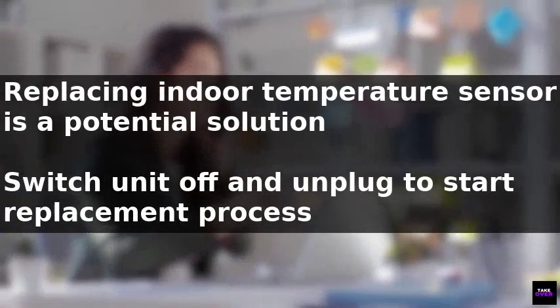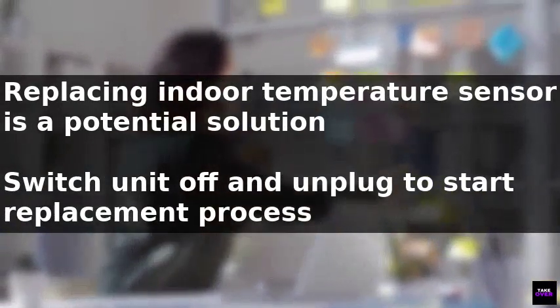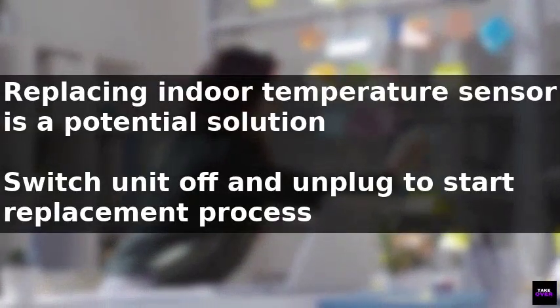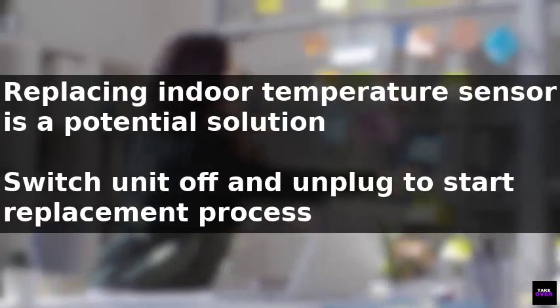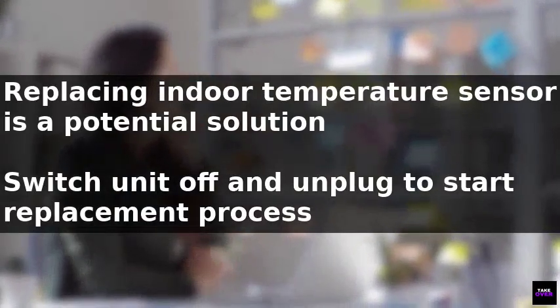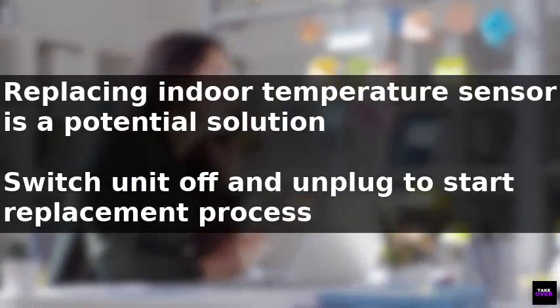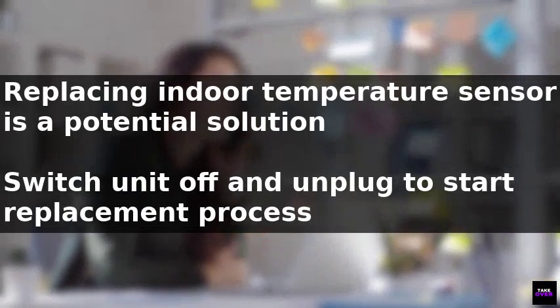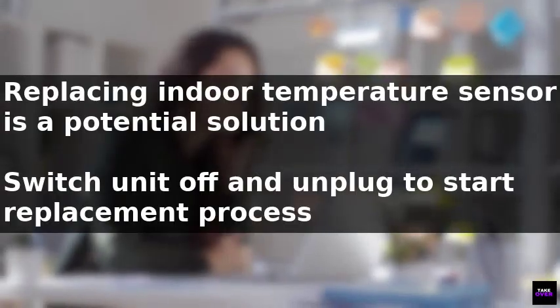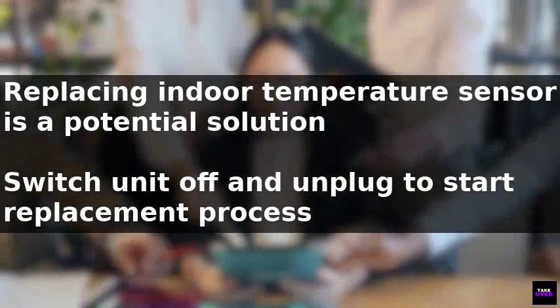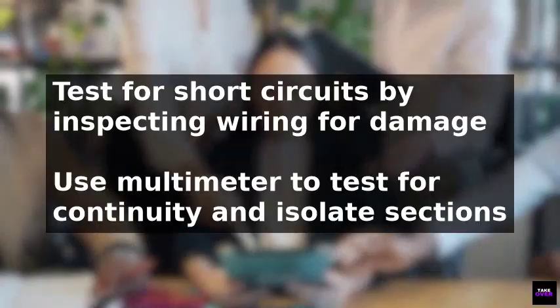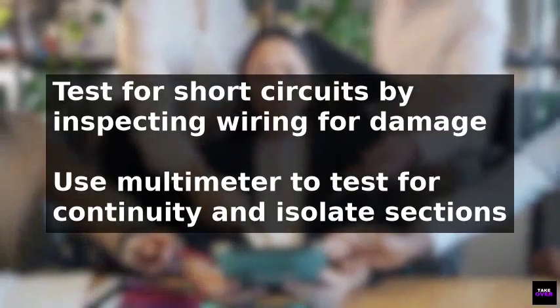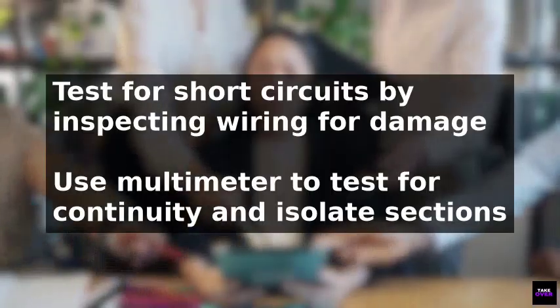This can be done by switching the unit off, unplugging it, removing the plastic cover, locating the temperature sensor, labeling the wiring, removing the faulty sensor, installing a new one, and then reinstalling the wiring harness and plastic cover. After completing these steps, the unit can be switched back on to test if the issue is resolved.